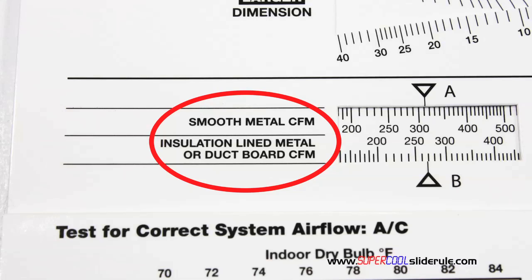The majority of technicians have never been taught that if the insulation is on the inside of the ductwork, you cannot size it with a regular duct calculator.